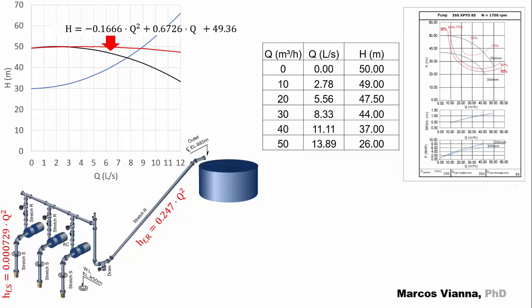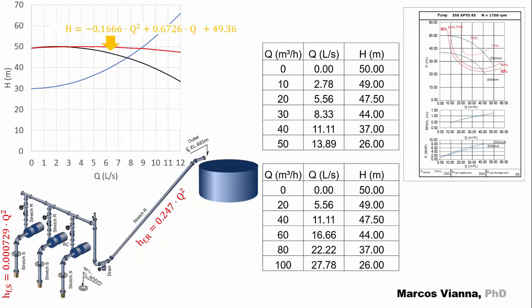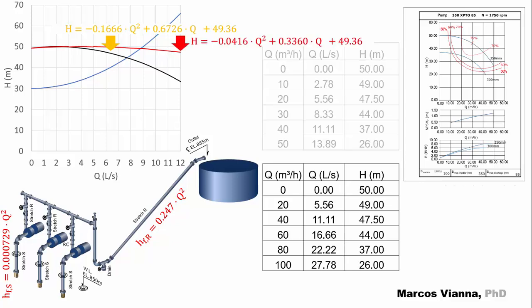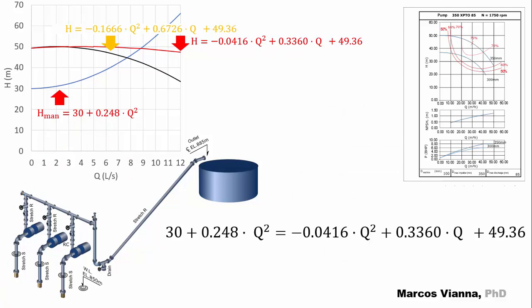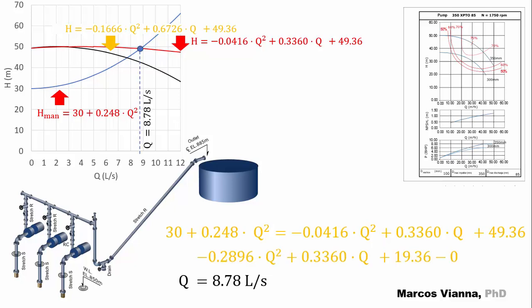In this table, you can see some pair of values for Q and H, extracted from the pump curve. So we can draw this new table, where the Q values are doubled. From these values, we can obtain this equation for H versus Q. As we know the characteristic curve of the system, which is the same, we put it together with the pump equation, obtain this equation, from which we can find the flow and the manometric head.